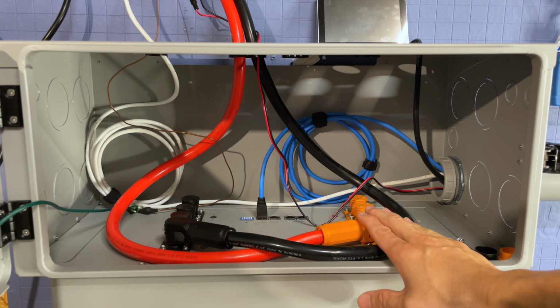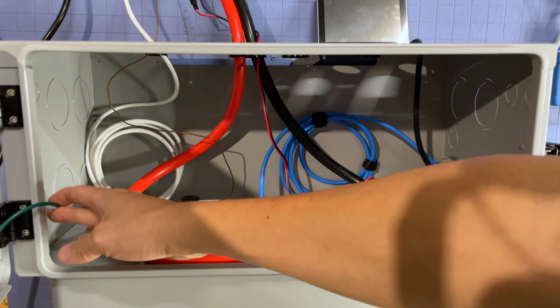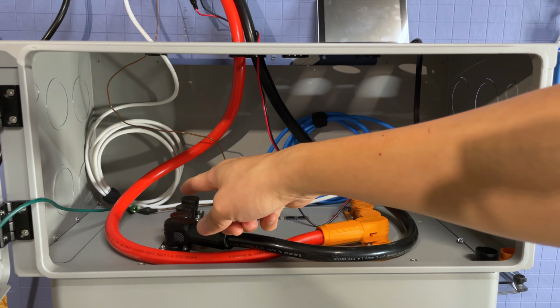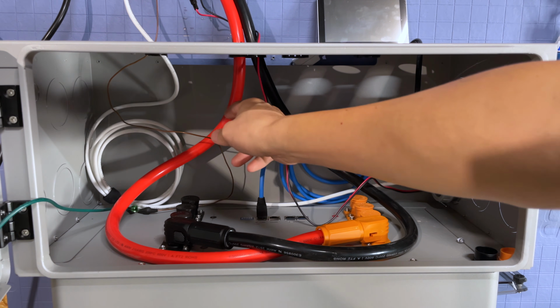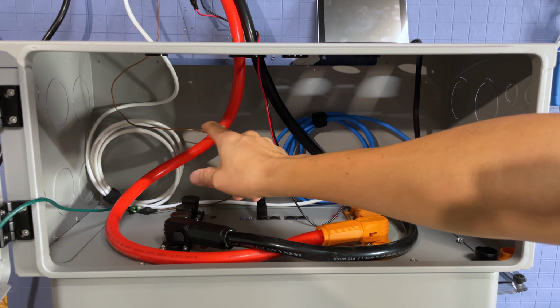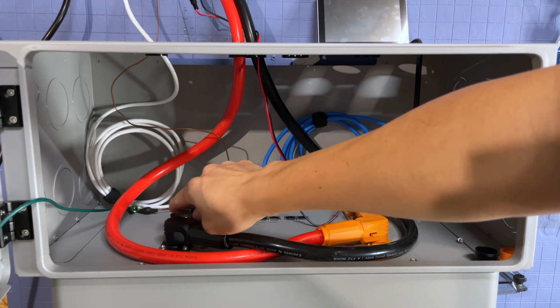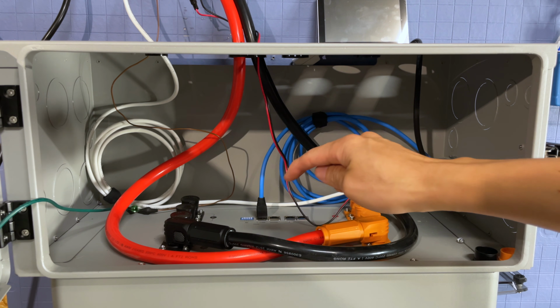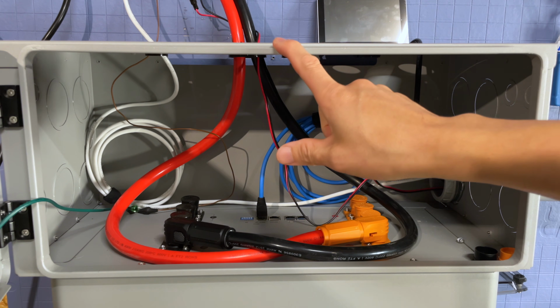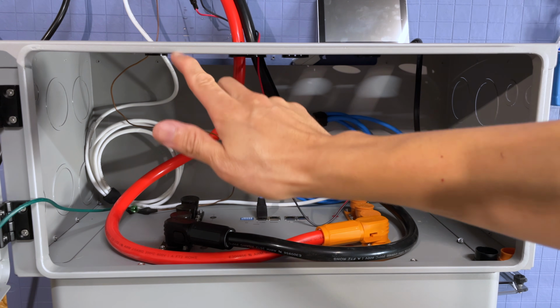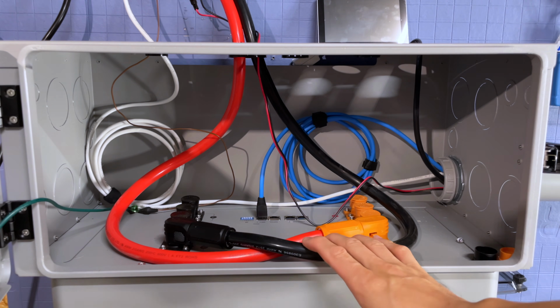On this door you'll see this green wire, which is for ground. There's a grounding screw in there. This copper cable, which is undersized but we'll fix that later, connects the metal parts of this battery, the conduit box, to the metal part of the inverter, as you saw up there on that grounding plug.